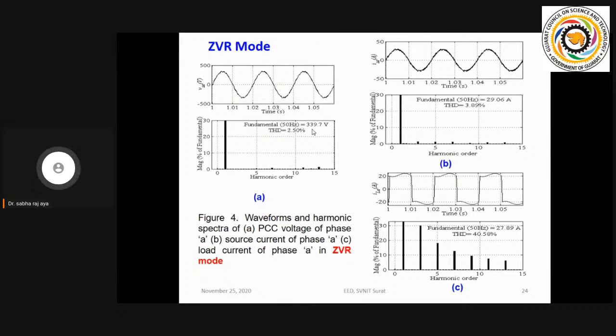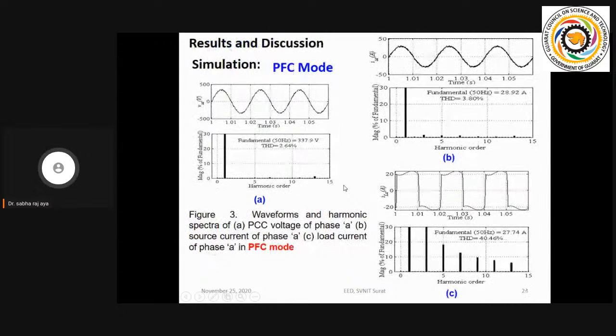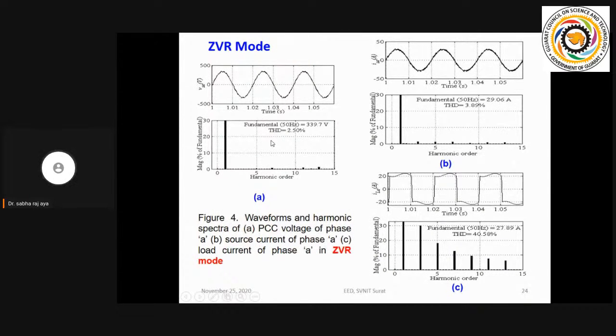The supply current and load current distortion are under limit only. And load current, how much? 40%. Supply current becomes less than 5%. Again you can see how we can make a difference. Here 27 ampere current is there, 28. But in this case we need more current to regulate the voltage. Here I got 29.07.